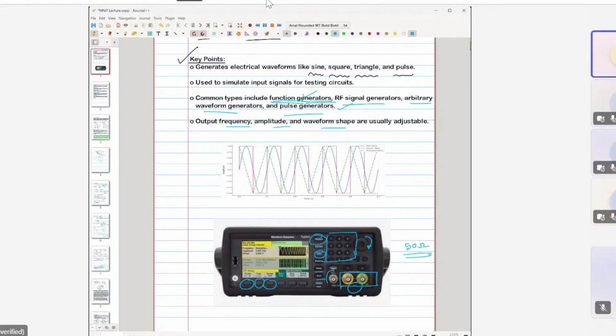Here this is for a different purpose, this is for syncing this signal generator, that probably we will not discuss here today. Here you can see there is a USB port. This USB port for this instrument can be used for transferring data or maybe loading data. For example, I have also mentioned that it can be used as an arbitrary waveform generator.